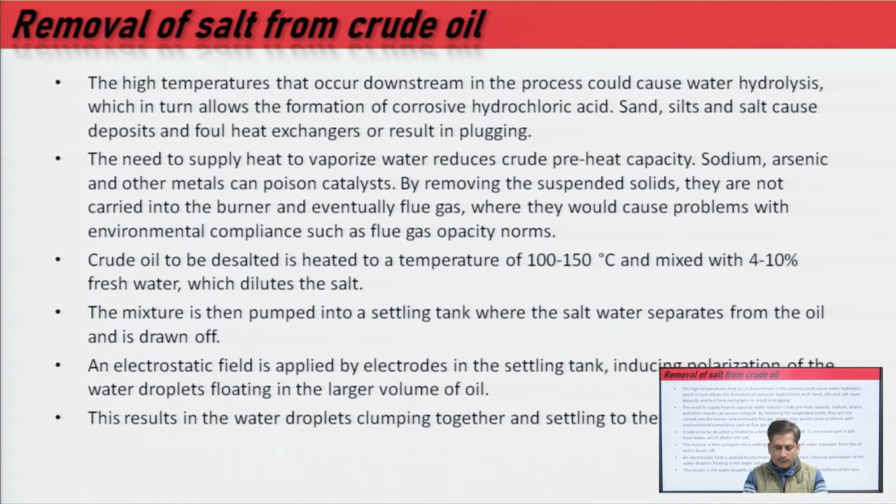Regarding removal of salt from the crude oil, the high temperatures that occur downstream in the process could cause water hydrolysis, which in turn allows the formation of corrosive hydrochloric acid. Sand, silt and salt cause deposits that foul heat exchangers or result in plugging. So, if it is not removed, at high temperature where the fuel will pass, those points will corrode more easily, and there will be some maintenance problems.